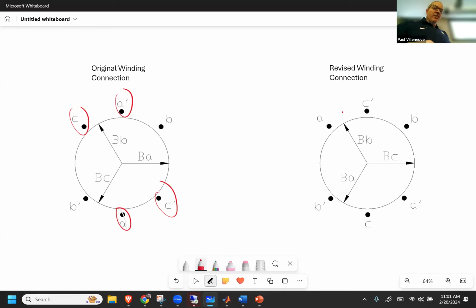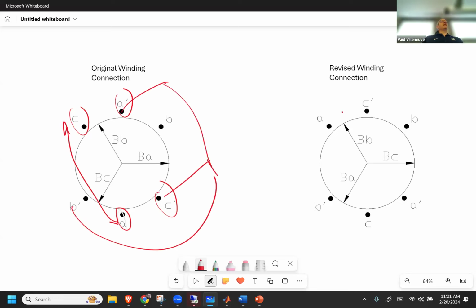Really, all we need to do is swap A and C. Why don't we need to swap A prime and C prime? Because normally those are all connected together - this is a delta or Y connected load. If you have a load with windings A, B, C, and A prime, B prime, C prime, you're not really swapping A prime and C prime around because they're connected to the same point. If it was a delta connection, it would change a little bit. But the reality is you just swap any 2 leads, A to C, and that's essentially all we're doing to get this configuration.